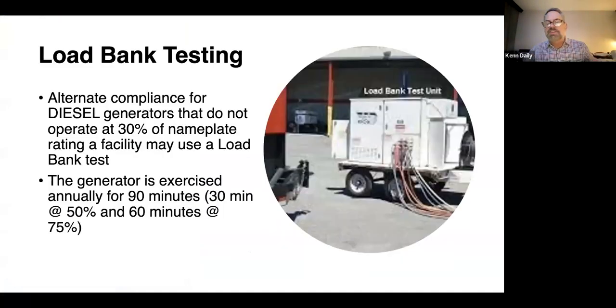So if you do have diesel generators running less than 30% on each of your monthly tests, once a year, as another form of compliance, you would have a load bank test for no less than 90 minutes. The device is running at pretty strong loads of 50 to 75%, which is really going to get rid of any oil and water buildup, wet stacking that may have occurred, because you're going to be circulating the oil and hopefully evaporating off any excess water.